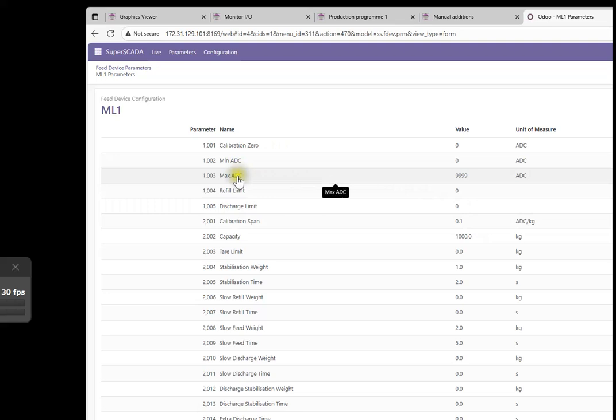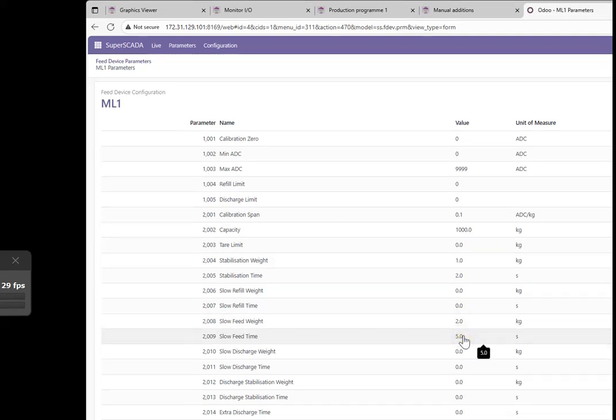Likewise, for the weighing in weight, there's a minimum and there's a maximum, just so that you can't go negative, and you can't go more than 9999. This is not a refilling scale, so it's blank there. And the discharge limit is not particularly relevant because this is a metering liquid. The stabilization weight, same thing again: when it stops, it's got to stop within 1 kilo for 2 seconds. Refill weight is not relevant because it's not a refilling type of scale. And slow feed: if it doesn't go up by 2 kilos in 5 seconds, then it generates an alarm.